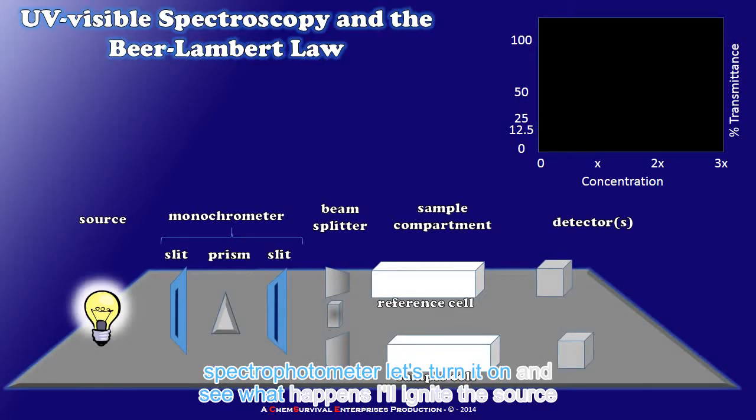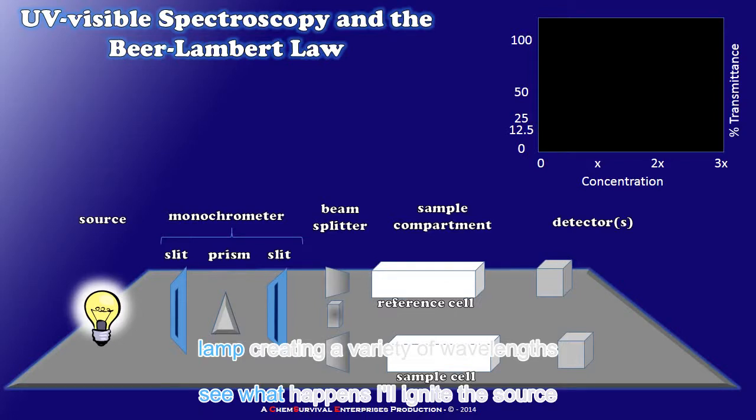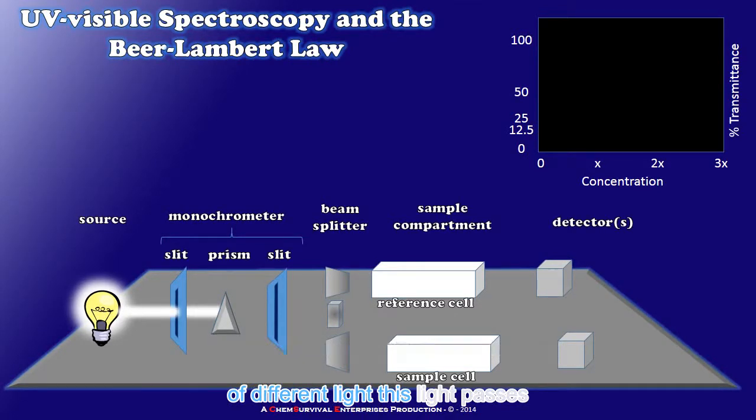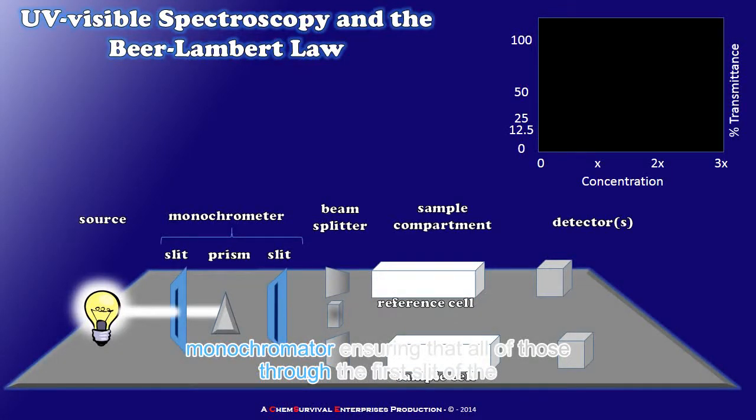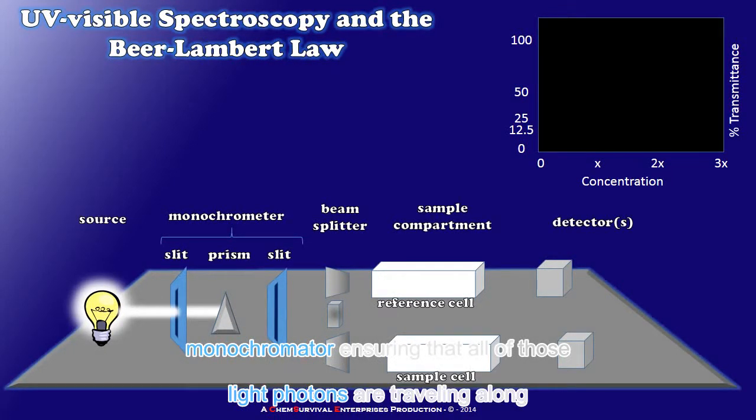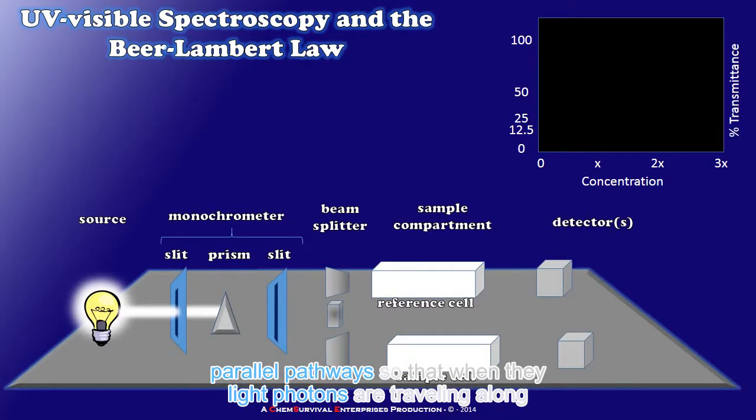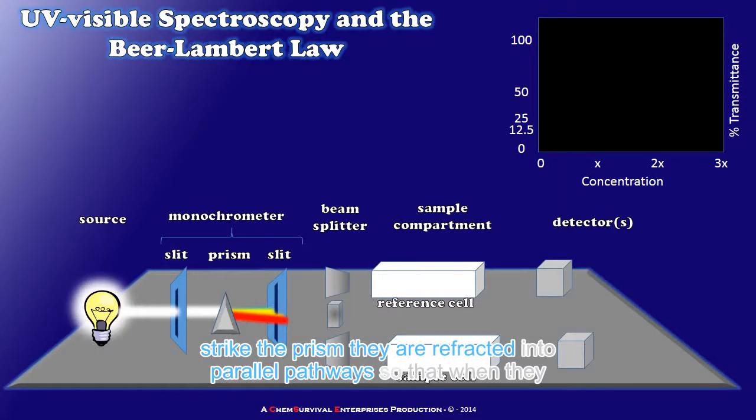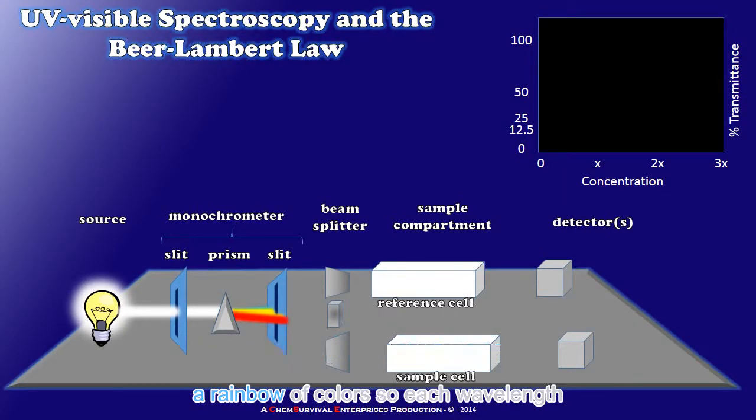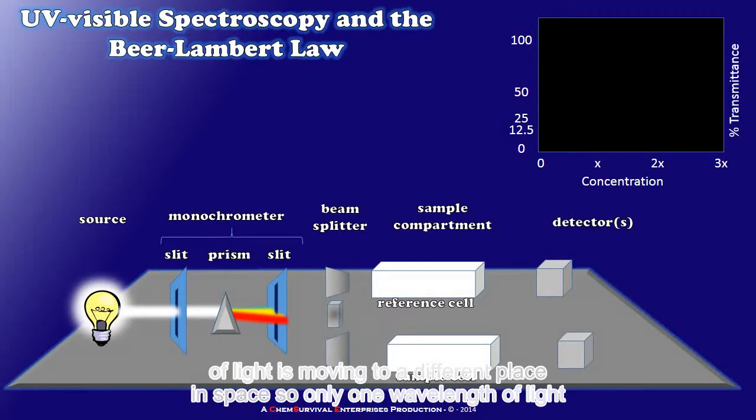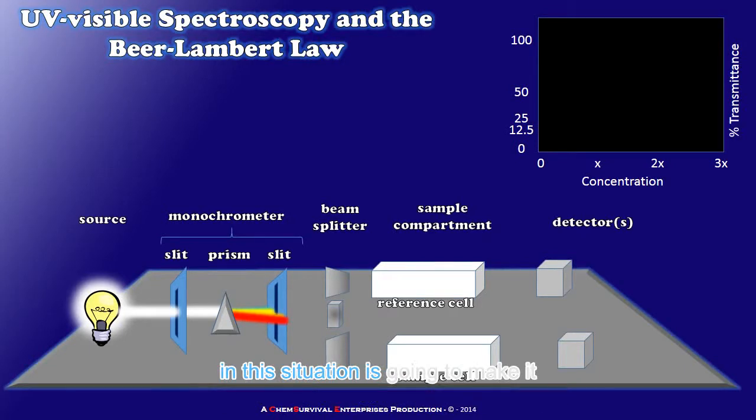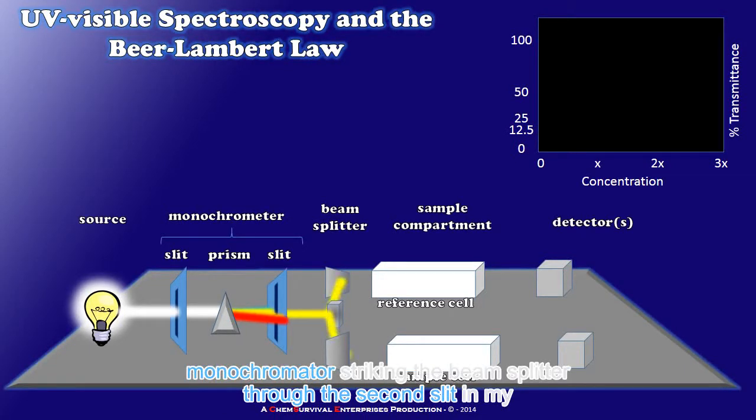So now that we've defined each of the smaller pieces within our spectrophotometer let's turn it on and see what happens. I'll ignite the source lamp creating a variety of wavelengths of different light. This light passes through the first slit of the monochromator ensuring that all of those light photons are traveling along parallel pathways so that when they strike the prism they are refracted into a rainbow of colors. So each wavelength of light is moving to a different place in space. So only one wavelength of light in this situation is going to make it through the second slit in my monochromator striking the beam splitter and becoming two beams of equal intensity.